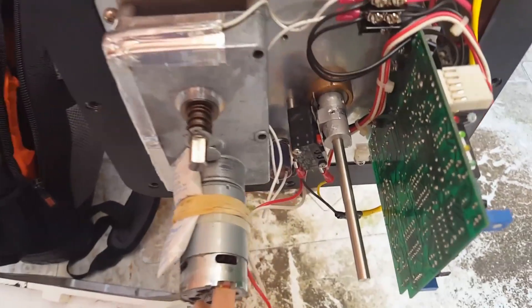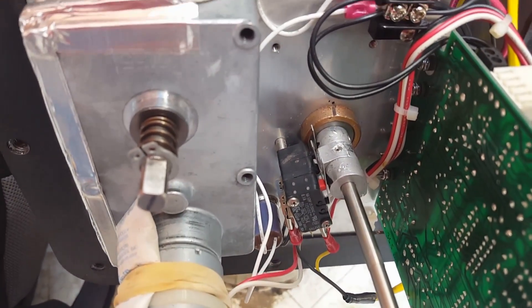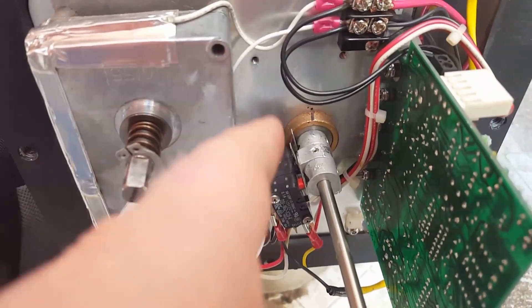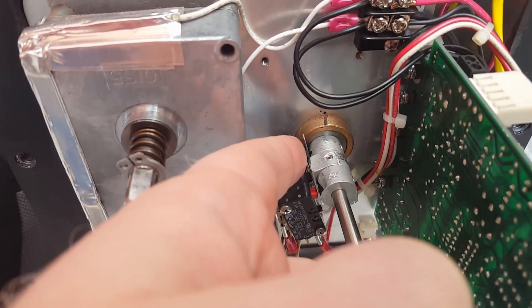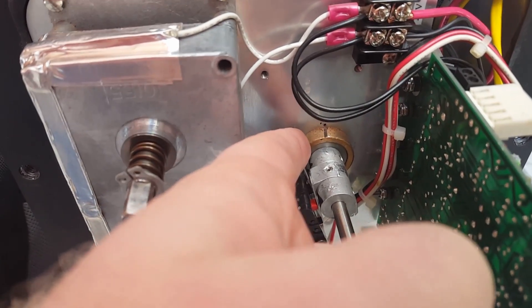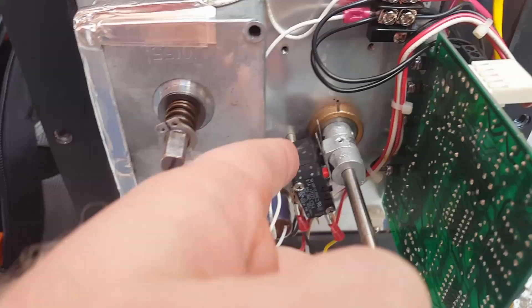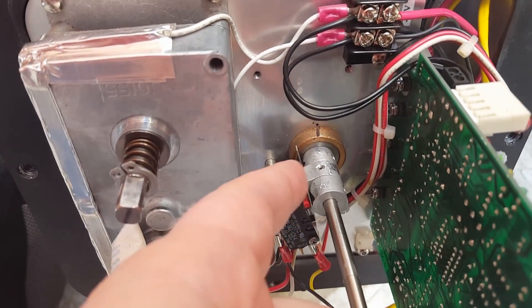What we're going to do is get in here and see if we can get these isolation valves closed off fully as they should be. Now we are going to test our adjustment. This switch here is the switch for fully open, and the back switch is the switch for fully closed. This is the status of this valve.